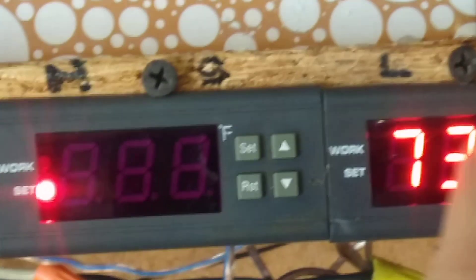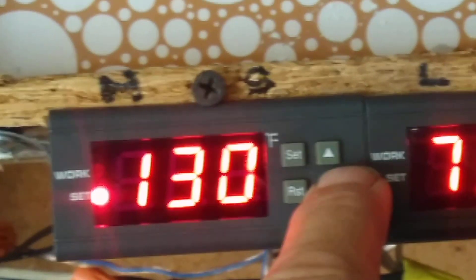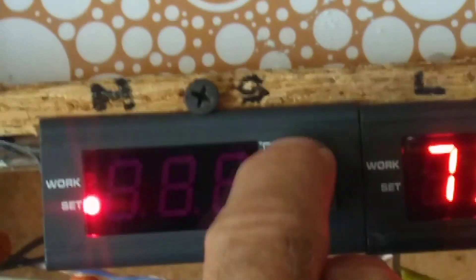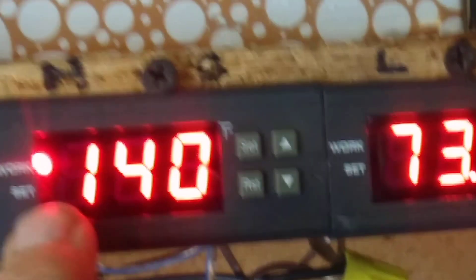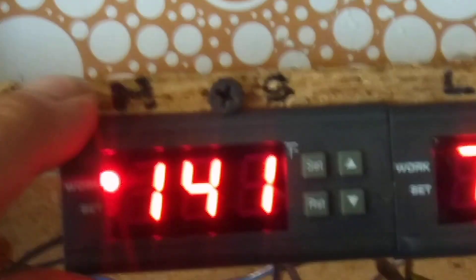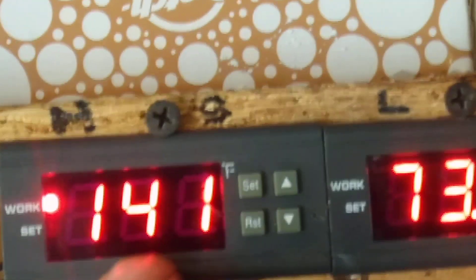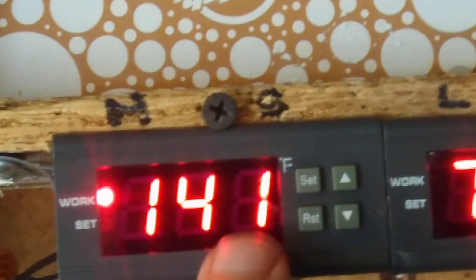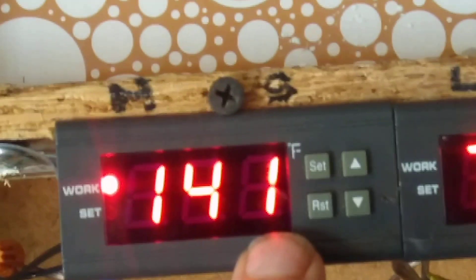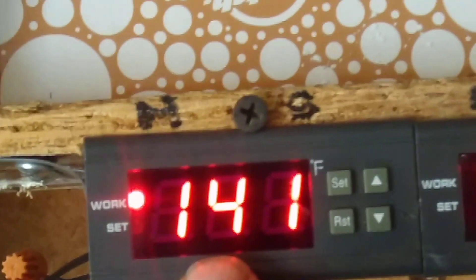I'll come over here to the thermostat and set this for 130 degrees. As you see, it just came on because I've got a spread. There's a spread on this meter that goes from 1 to 25. If I set the spread at 10, that means it'll take the collector temperature of 140 degrees for it to turn on the pump to circulate the water out of the collector into the water heater. First thing in the morning, you want your spread down low, like 10 or 15 degrees.